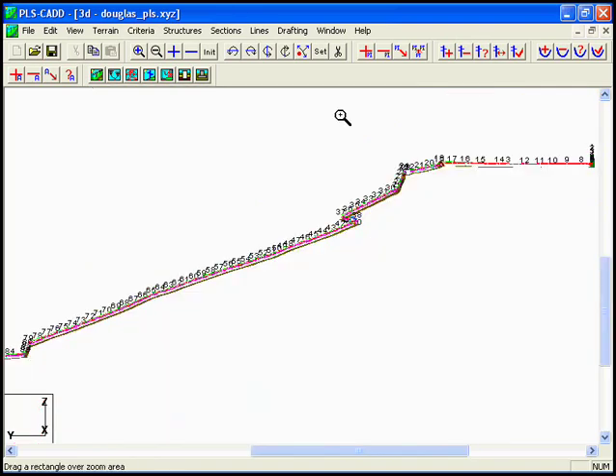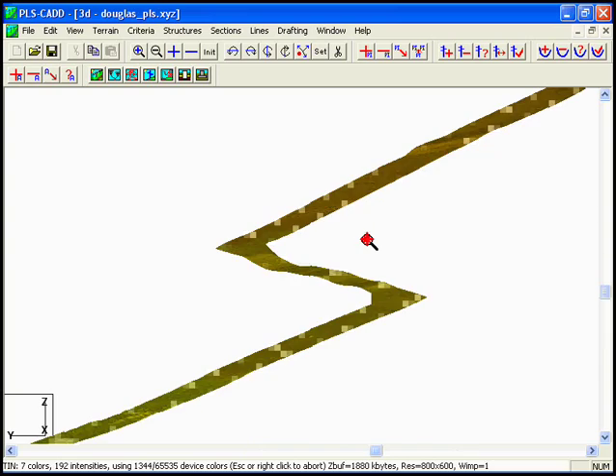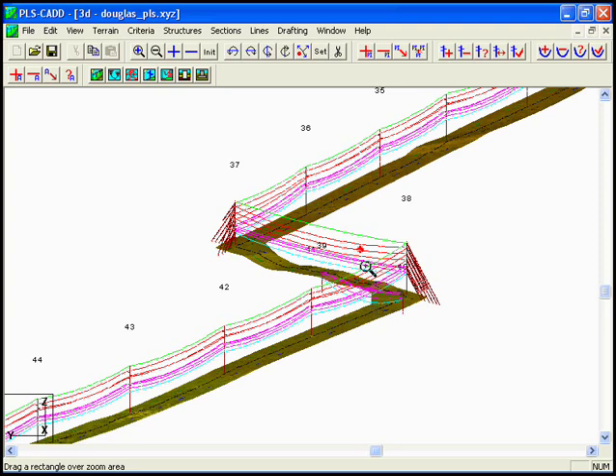Backing out to our entire three-dimensional view again, we'll re-zoom in on this particular area, and we can see that we have our distribution underbuild, which visually looks like it's getting kind of close here. We also have a distribution crossing underneath our transmission line in this particular area. So let's run this report again to find out if we have clearance violations between our 115 kV transmission and our 12.5 kV distribution underbuild and crossing.